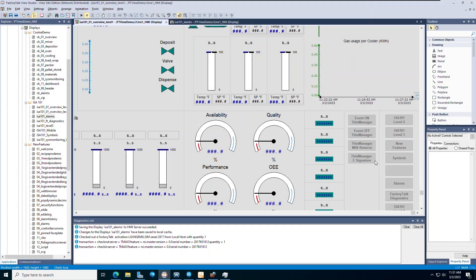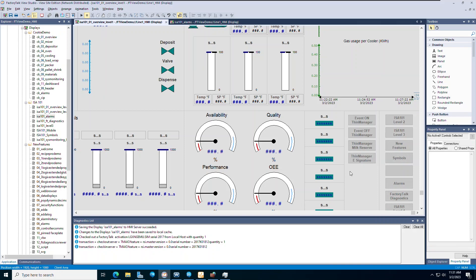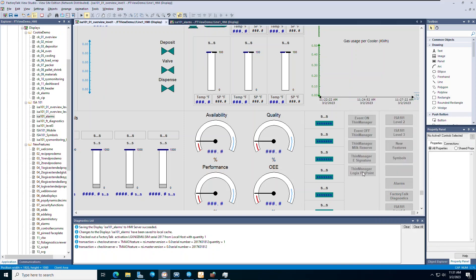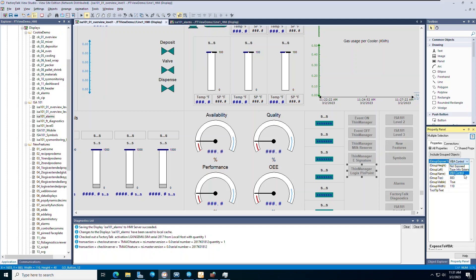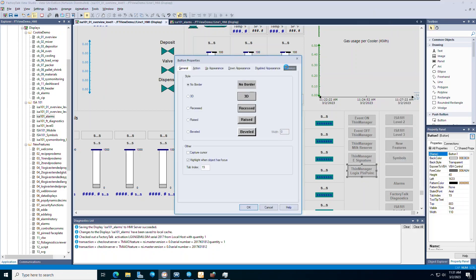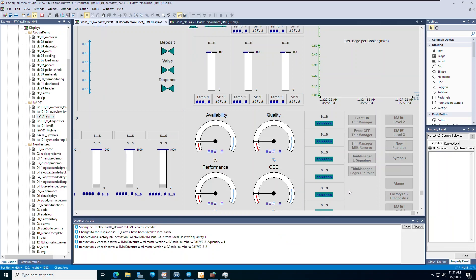Now we will create the ThinManagerLogix Pinpoint button on the main overview display within View Studio. You can copy and paste a different button or add a new one. In the control panel of the button, change the value of the Expose to VBA field to VBA control. Within the properties of the button, you can modify the appearance and name as desired. In this case, our button is referred to as button 1.